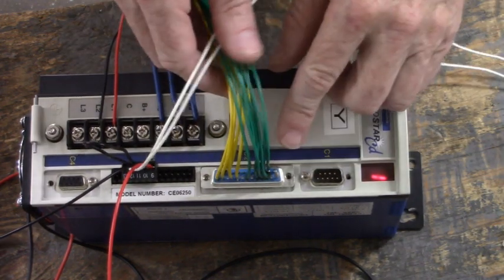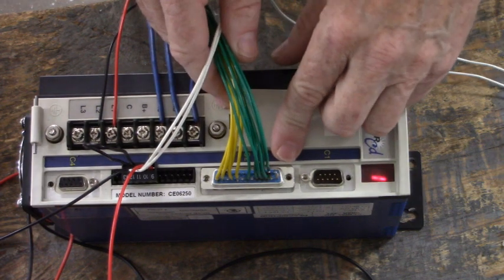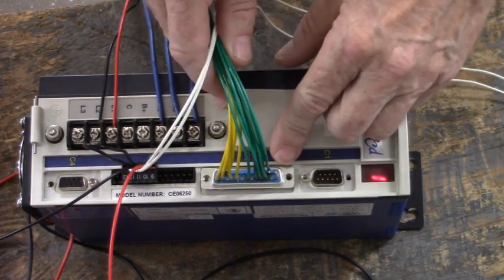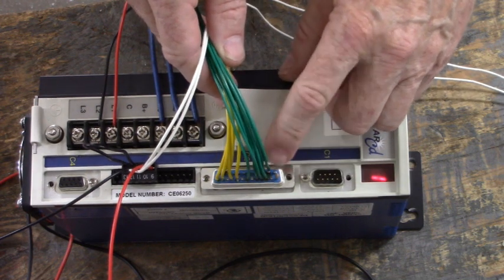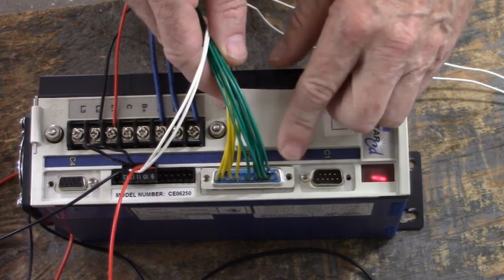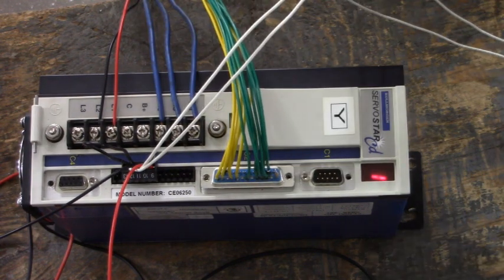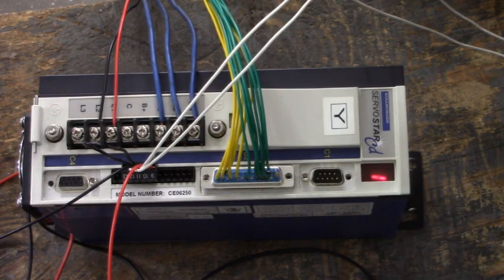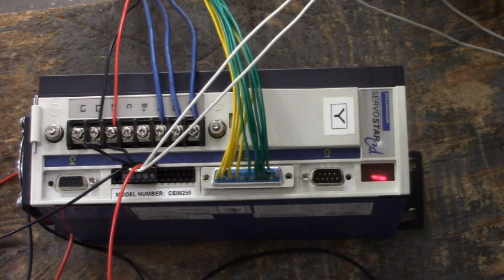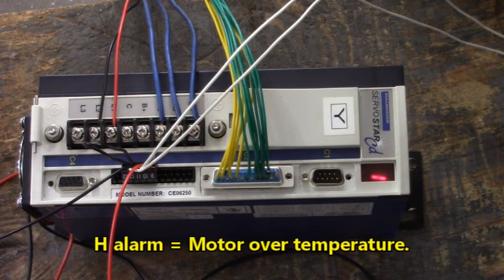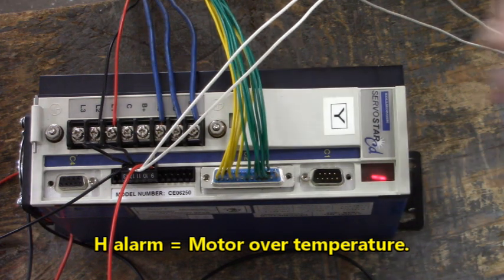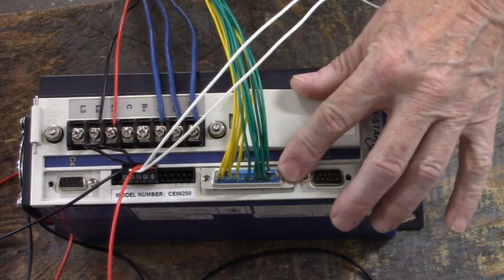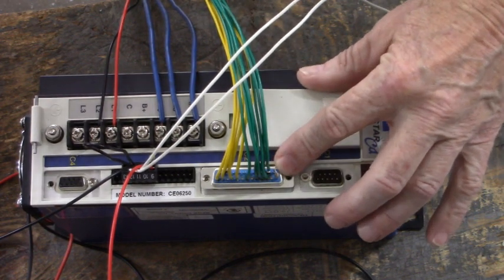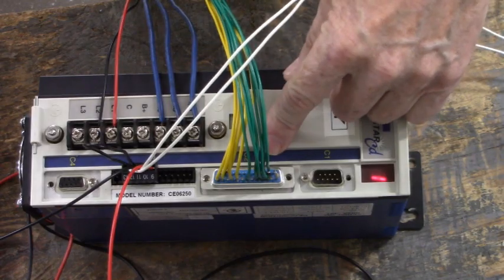Now, over here on pin 13 and 25, that's your motor thermal input, and I have it jumped out with a 100 ohm resistor. If your motor overheats, the alarm that you're going to get is H, motor over temperature, motor overload caused overheating. But I have it simulated with this 100 ohm resistor from pin 13 to pin 25 on that C2 connector.